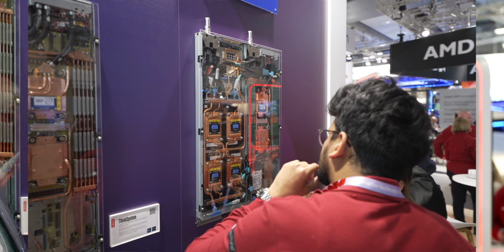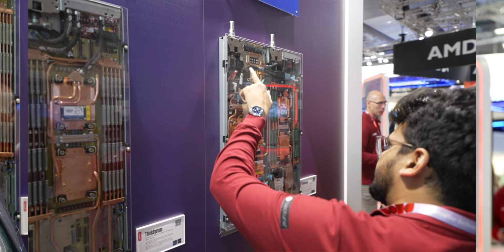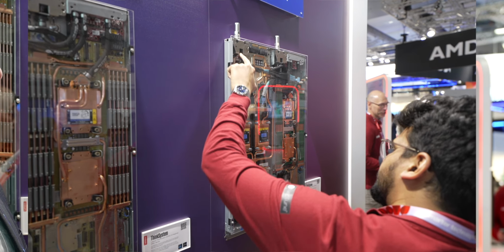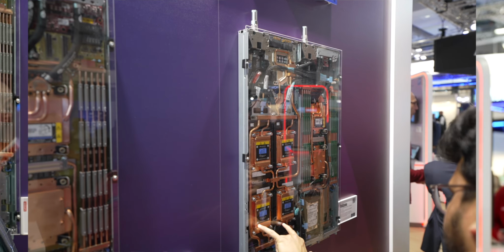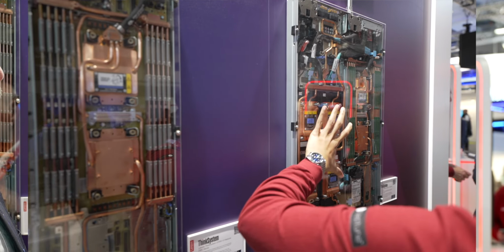As long as you make sure there's a delta between the water temperature and the maximum junction temperature of your processors and GPUs, you're always cooling down. We base the flow rate of the water through the plumbing and piping on the type of processor, the TDP value of the processors and GPUs, and the type of workload you're deploying, to make sure enough water is flowing through the copper to cool down the heat-dissipating component.